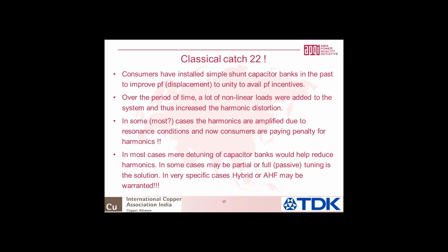So one of the simplest solutions, in most cases, could be a mere detuning of the capacitor bank, which would help reduce the harmonics. I've seen cases where you just add a 7% or 14% reactor and the THD comes down by almost 10-15%. In some cases, where you're really generating a lot of harmonics, where we have drives or inverters and UPS inside, you need a passive harmonic filter. A partial tuning or a full tuning is good enough. And in very specific cases where you have multiple high-frequency harmonics, where you also want to correct for unbalance, maybe you should use a hybrid or an active harmonic filter.